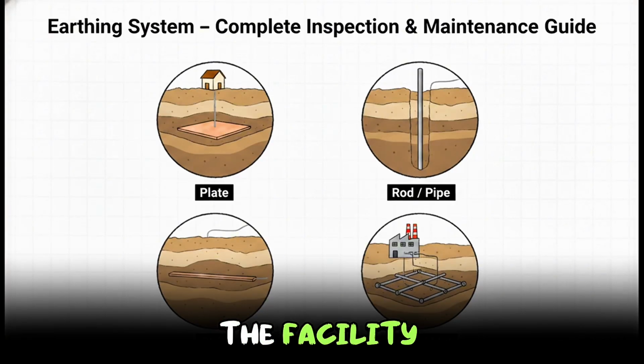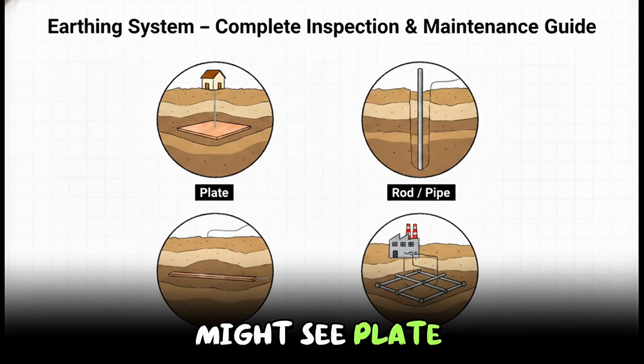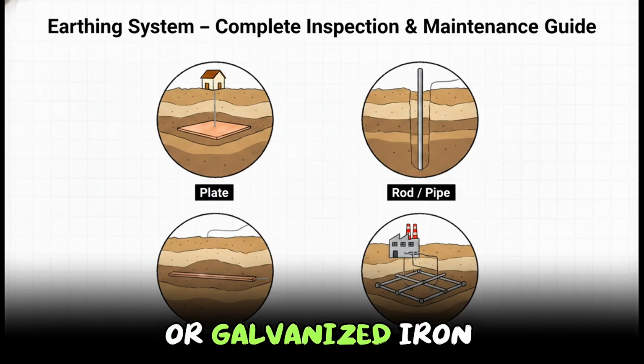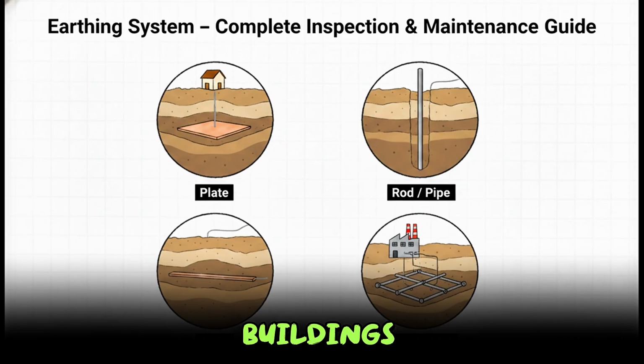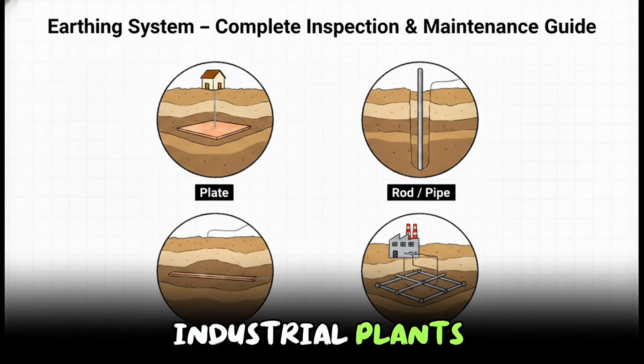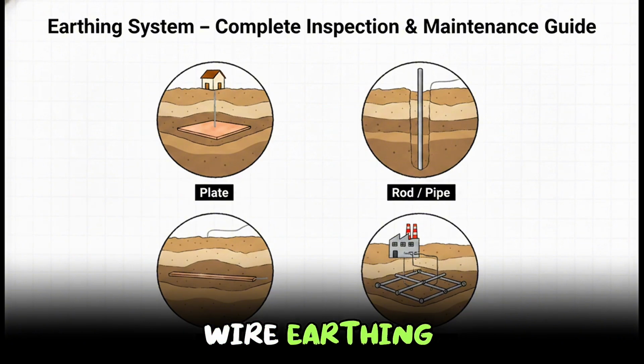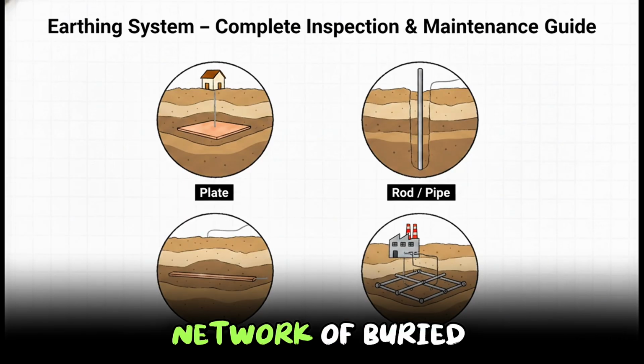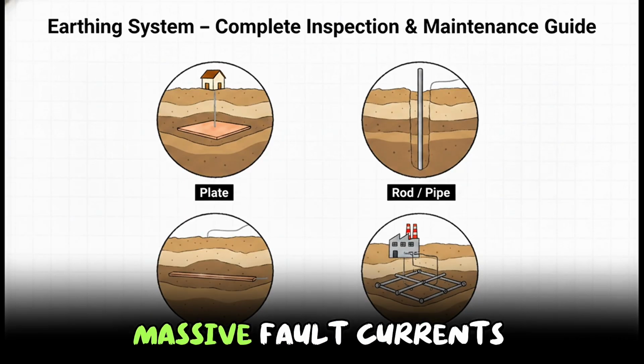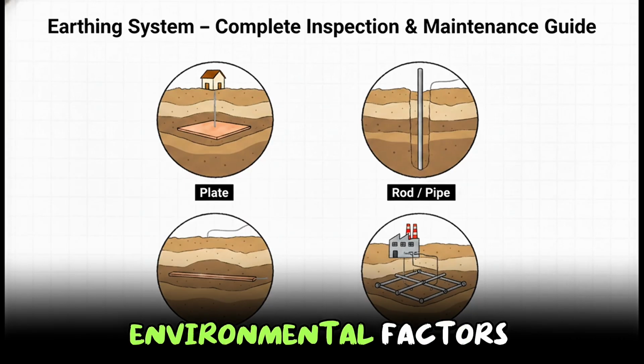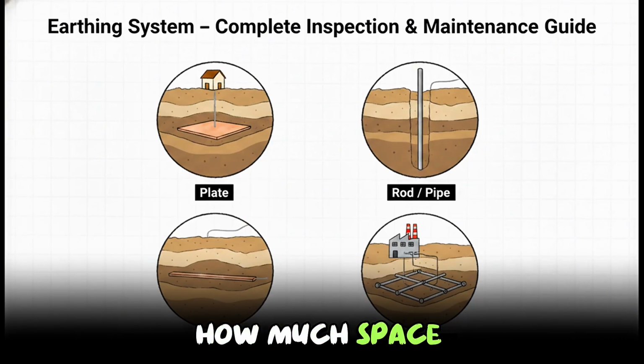Now, depending on the facility, the physical configuration of that earth electrode totally changes. You might see plate earthing, usually using copper or galvanized iron, which is super common in residential buildings. Pipe earthing is probably the most widely used because it's economical. If space is tight, a driven rod is your best bet for sure. For substations and industrial plants, you're going to see buried strip or wire earthing. And for massive power plants, they use a grid or mat, literally a vast network of buried conductors to handle those massive fault currents. It really all comes down to environmental factors, your budget, and how much space you've got.